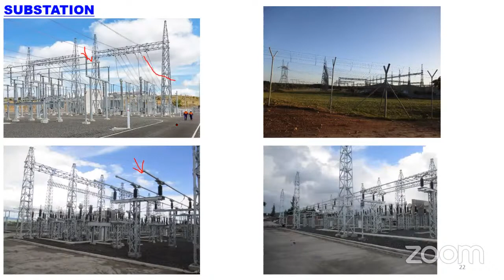The key role of the substation electrical engineer: understand the client requirement, do the modeling of the station, select the equipment and determine the quantities required. Then handle auxiliary items like earthing, grounding, light fittings, control cable quantities, and cable trays. All this work comes into the picture for the electrical engineer, who also needs to coordinate with the civil and structural engineer and with the product supplier providing the transformer or other switchgear equipment.